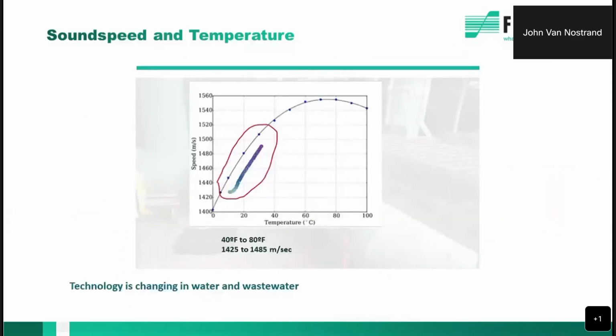So with that sound speed measurement as well, remember I said about 1470 is 70 degrees Fahrenheit. What we can actually do is take a measurement of the water when we install the meter, and then we can put an output on that sound speed measurement to give us the temperature of the water. So it's accurate within the range of water systems. It's accurate to about plus or minus 1 degree. I don't know if it's important to anybody, but there are times when you might want to actually measure the temperature, especially if you're doing chloramines and you have a bio outbreak.